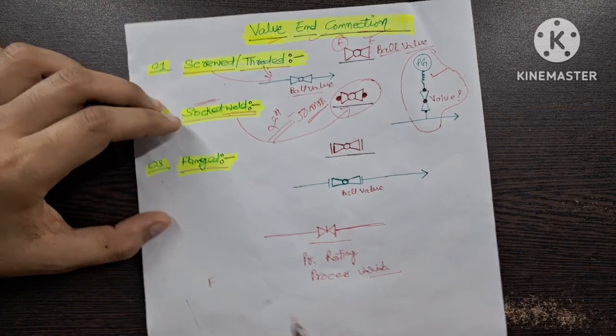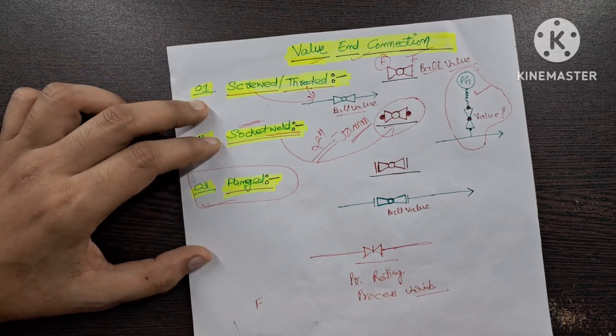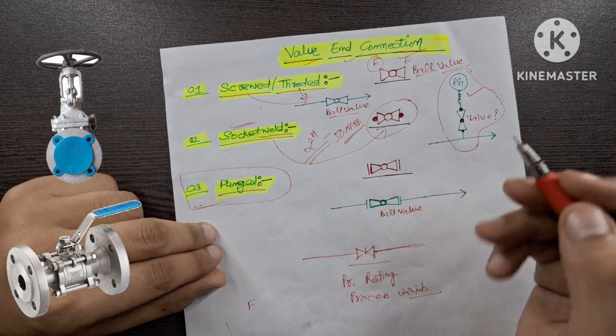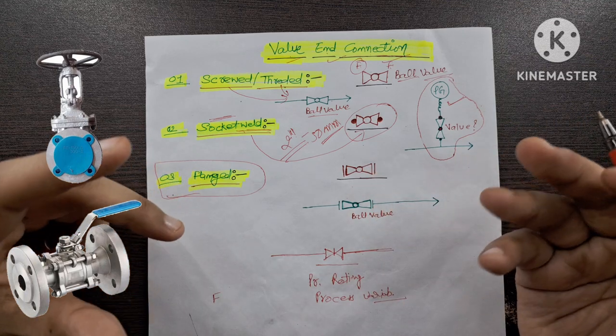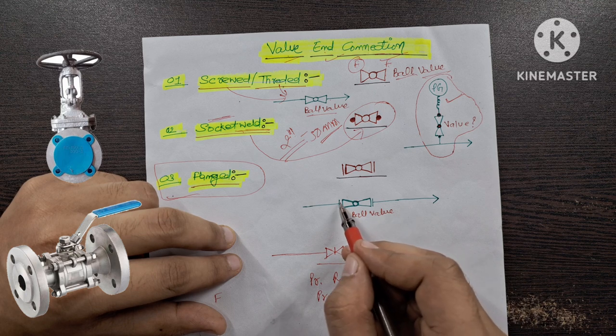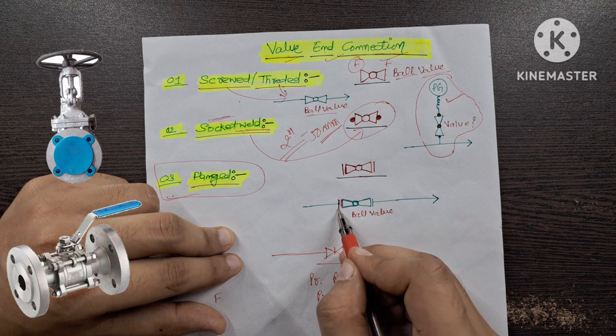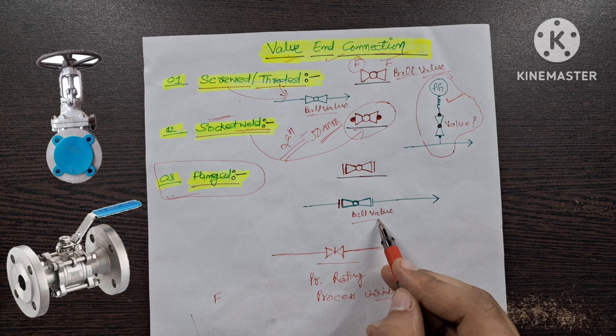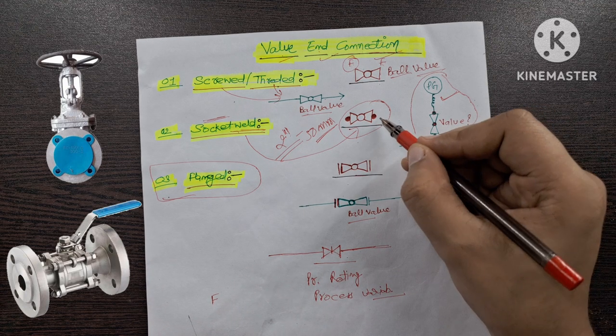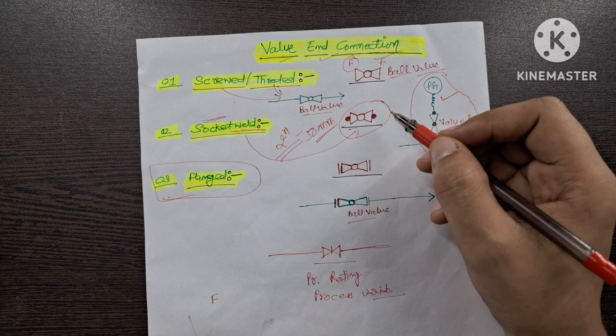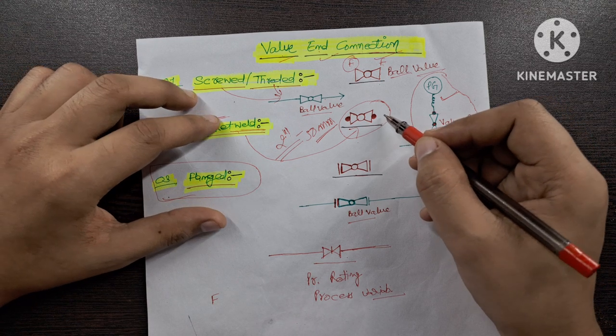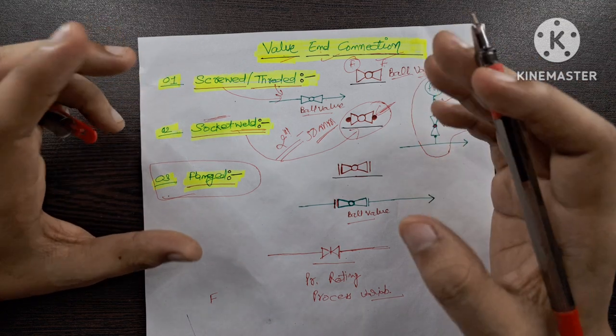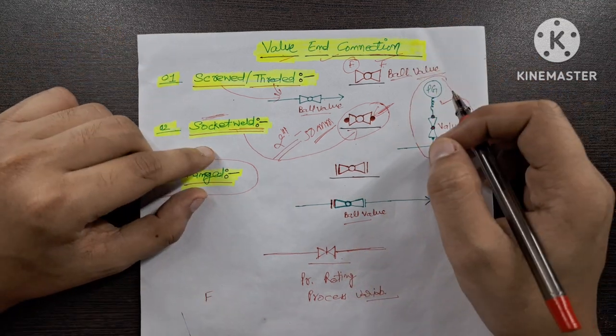The most commonly used end connection is the flanged type. Both sides — your pipeline as well as your valve — will have a flange, and then you connect both with nuts and bolts, as simple as that. These flanges connect together, but in this case the leakage chances are a little bit high. In the case of socket weld, the leakage chances are very, very rare. That's why in hydrogen lines and steam lines we use socket welded valves. These are the main types of end connection we see in industry.